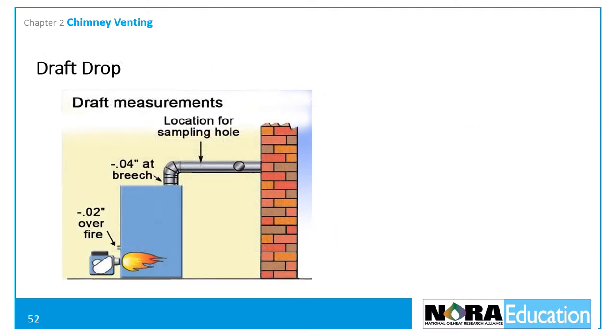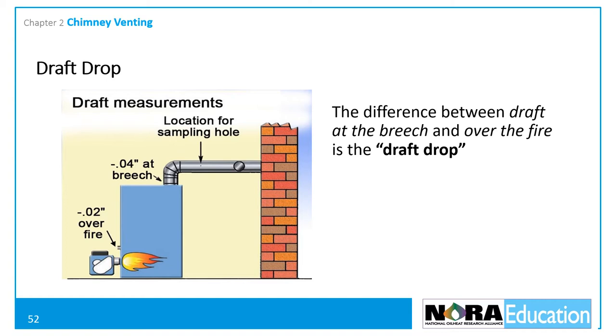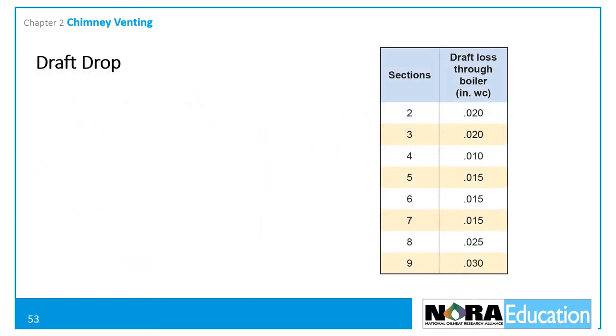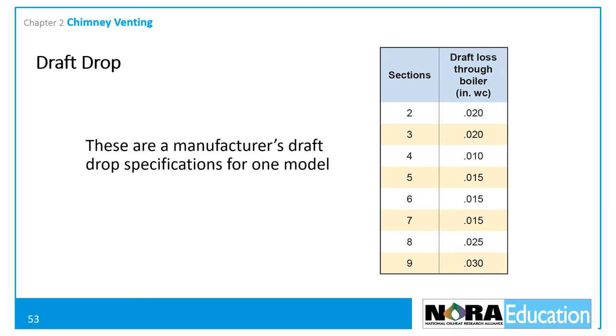Normally is emphasized here because the manufacturer's guidelines must be followed, and there are some oil-fired appliances that require positive over-fire draft. Manufacturers also specify what the draft drop through the appliance should be. Draft drop is the difference between the draft over the fire and the draft at the breach. For example, if there are negative 0.04 inches of draft at the breach and negative 0.02 inches over the fire, the draft drop is negative 0.02 inches of water column.